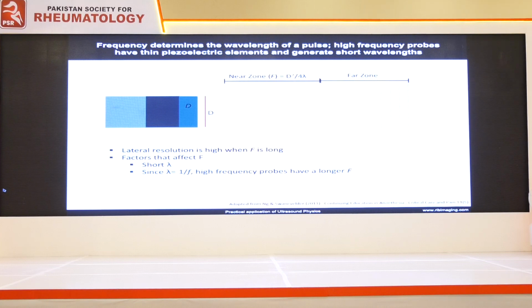But essentially, the key thing about all this is that your sound waves are produced in parallel lines, and the maximum resolution that you will have will be in the period when the sound waves are parallel to one another. Beyond a certain point, the sound waves start to diverge, and at this point, the information that you receive from the far zone distorts your image. So if you want to know the detail of something, you want to look at it where your sound waves are still parallel. By the time it gets to this point here, the sound waves are divergent, and so the resolution of what you're looking at will become worse. So this is a very important thing.